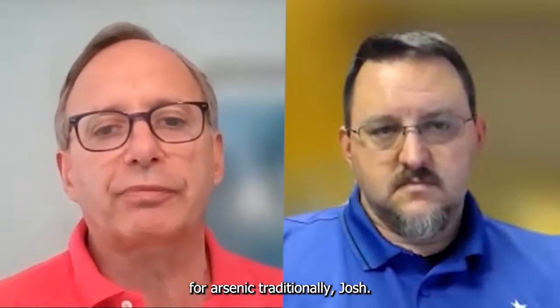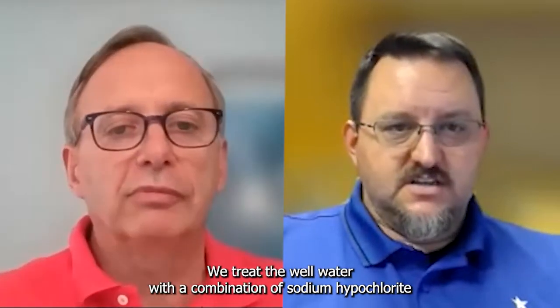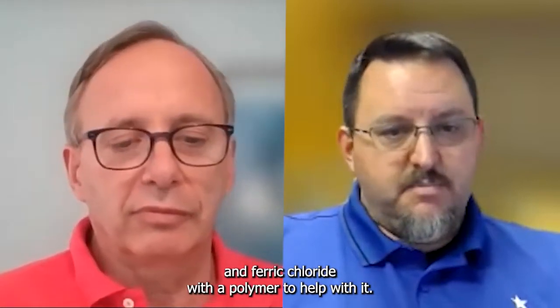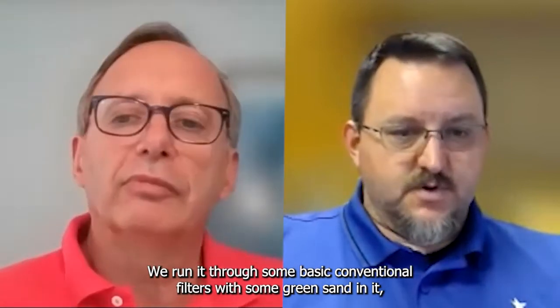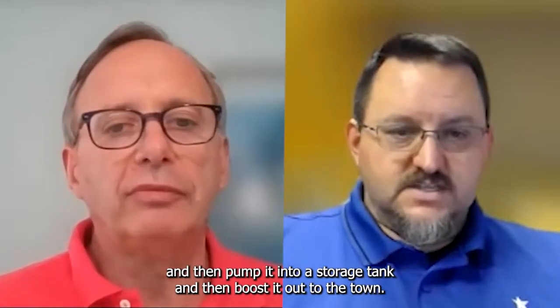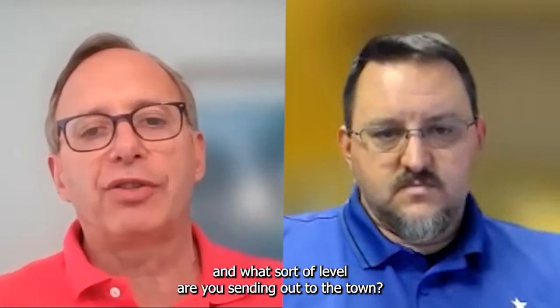So maybe you could just describe a bit about how you've been treating for arsenic traditionally, Josh? Yeah, traditionally we have 2 wells on site. We treat the well water with a combination of sodium hypochlorite and ferric chloride with a polymer to help with it. We run it through some basic conventional filters with some green sand in it, and then pump it into a storage tank and then boost it out to the town now. Great. And what sort of level of arsenic are you having to treat for, and what sort of level are you sending out to the town?